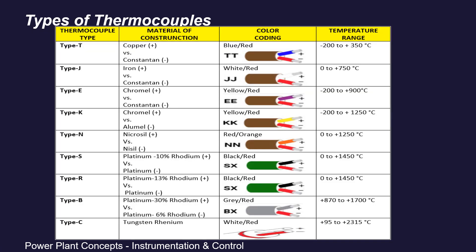Coming to the types of thermocouples: as per ANSI — the American National Standards Institute — and ASTM, there are 9 main thermocouple types: Type B, E, J, K, N, R, S, T, and C. The most commonly used in the power plant industry is Type K — chromel-alumel, with alumel containing 95% nickel. It is durable and has a wide temperature range from minus 200°C to plus 1250°C. Thermocouples can be identified by their color coding; for Type K, the color coding is yellow and red. All thermocouple types, their materials, color coding, and temperature ranges are listed in this table.